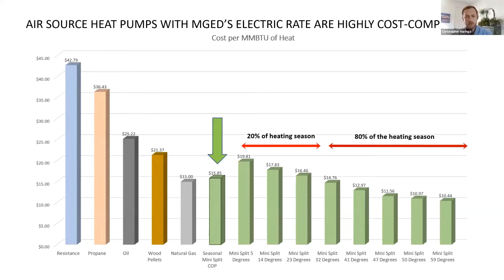I would note, Sandy, as well, if you look at the 80% of the heating season section, between 32 degrees and 60 degrees, the heat pumps are providing that heat at a cheaper cost than you can with natural gas. So we have a big portion of the heating season that you can heat more cost effectively with the heat pump.